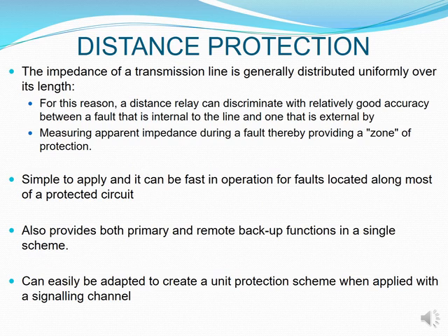When we talk about the impedance of our transmission line, we usually talk about an impedance that is spread out throughout the length of that line. So if you have a 150-kilometer line from where your first substation is, the impedance will be spread out through that line. At different points of that line, for example at 50 Ks, you will have a different impedance than what you have at 100 Ks and what you have finally at 150 kilometers.